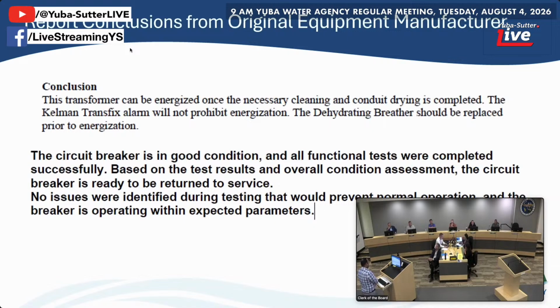These are snippets taken from the final results that we received a couple of weeks ago. These are OEM words that this equipment is ready for service. There are no structural issues with the devices on all the windings and core. Testing is good, and they can be put back in service and energized, along with some minor issues that we ran into. We found some debris in the conduits, which we need to clean, some heater issues, and some coolers need to be cleaned additionally. We're working on those job plans, and these issues will be taken care of in the coming weeks.